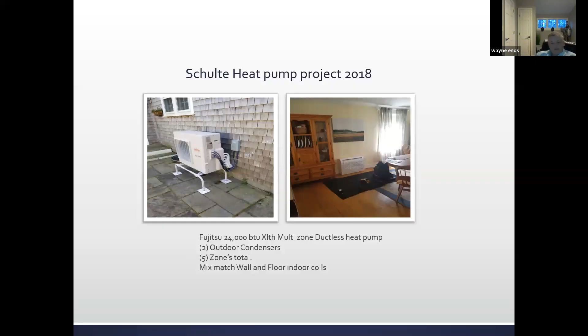This is a project on Nantucket, the Schulte heat pump project from 2018. I installed a 24,000 BTU Fujitsu XLTH unit — XLTH meaning extra low temperature. The customer had oil heat, and between 2017 and 2018 she gave me her electric and oil bills. By the end of 2019, she had a 24% savings from installing air source heat pumps.